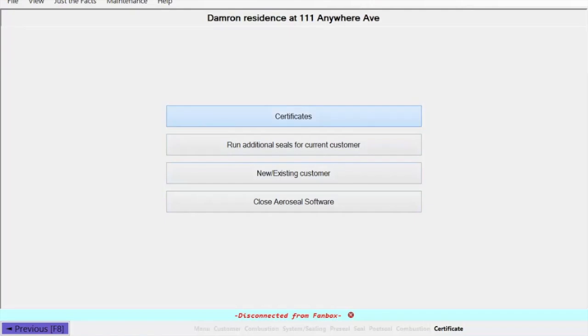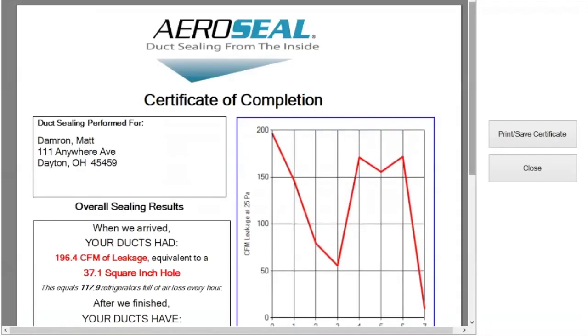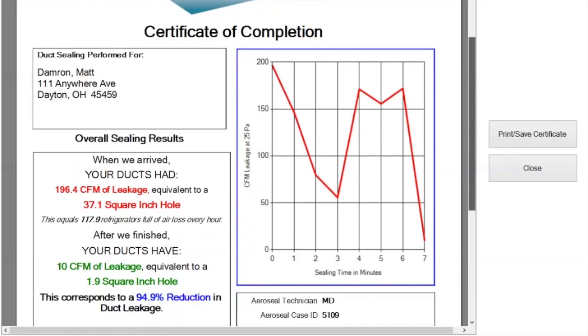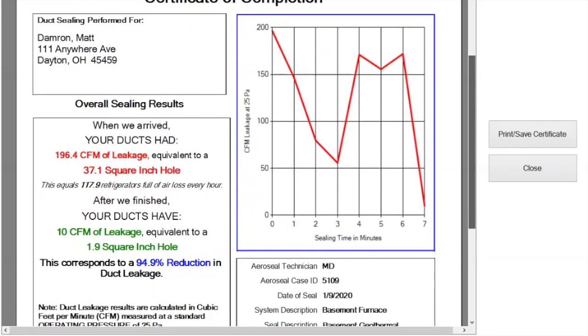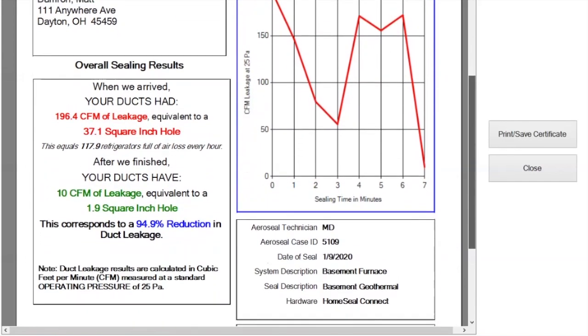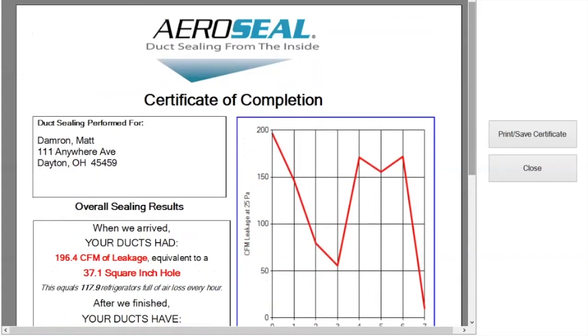So we're going to select certificates. It's going to bring up your post seal certificate report. This is what you want to share with your customer. It's going to show you in this case that we went all the way from 196 CFM down to 10, so we had a great seal and want to be able to share those results with our customer.